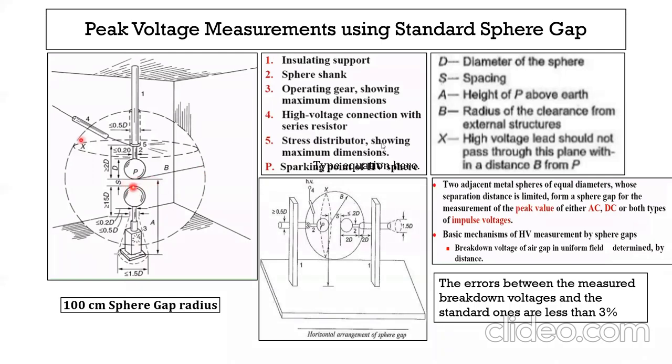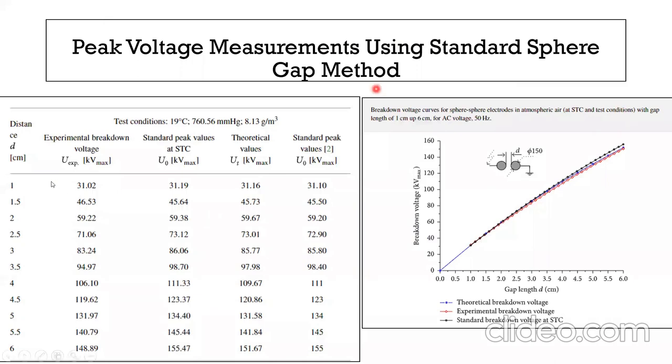What is important here is one upper sphere is a fixed one and the lower sphere is movable. You can push this lower sphere upward and downward so that you can change the spacing. Basic mechanism of high voltage measurement is by sphere gap. Breakdown voltage of air gap in uniform field is determined by the distance. So distance versus voltage, a table is prepared.